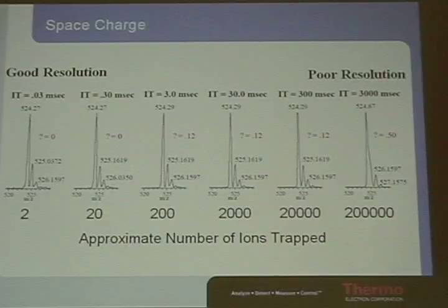And what causes them to leave? What electricity, what voltage causes them to leave? The RF oscillation, the amplitude. Which RF? The quad. Okay, so the dipolar causes them to leave. Causes them to eject, right. Now, the quad causes them to reach the dipolar. So the dipolar doesn't change. That causes them to leave at the right time. So obviously what's happening here is some of the ions are reaching the dipolar at a different time period because they're at a different frequency. So space charge is some ions moving at a slightly different frequency than their counterparts at the same mass.